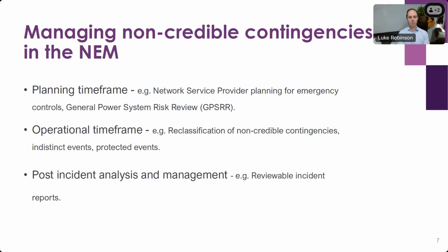When it comes to non-credible risks, and again, we'll use this term throughout the presentation, we're referring, in general terms, to high impact, low probability events. Those things which you're not operating the system to cater for, but which still do have a calculatable probability of occurring. And there's a few different ways that we'll take into account those non-credible contingency events. In the planning time frame, some examples here, network service providers are evaluating the potential for major events to lead to cascading failures, and they're planning for emergency control schemes.